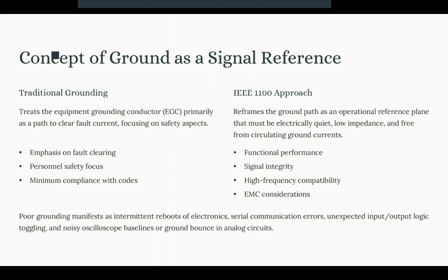Now, we have the concept of the ground as a signal reference. Let's talk about it. Traditional grounding basically treats the equipment grounding conductor primarily as a path to clear the fault current. It is designed to carry the fault current temporarily during the fault event. The impedance values on those systems are chosen for fault current magnitude, not for signal stability, and there is no consideration of high frequency transients for logic circuit integrity.